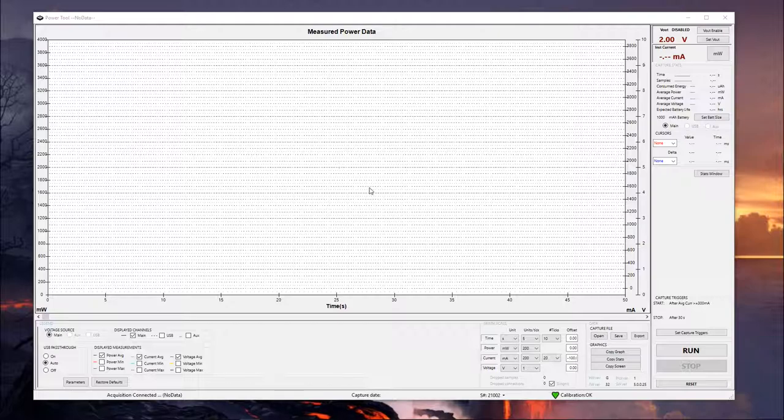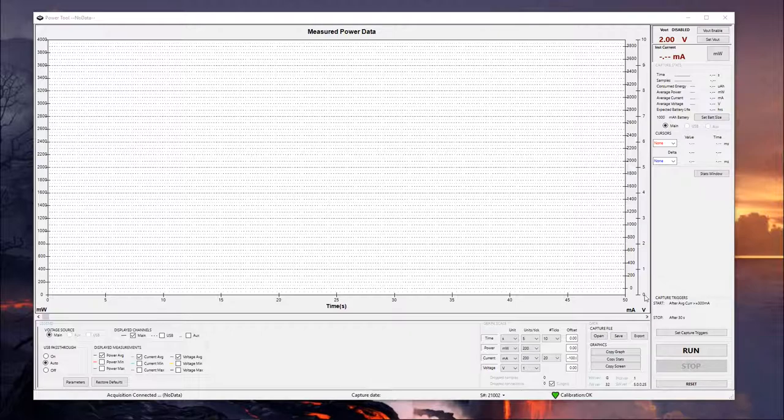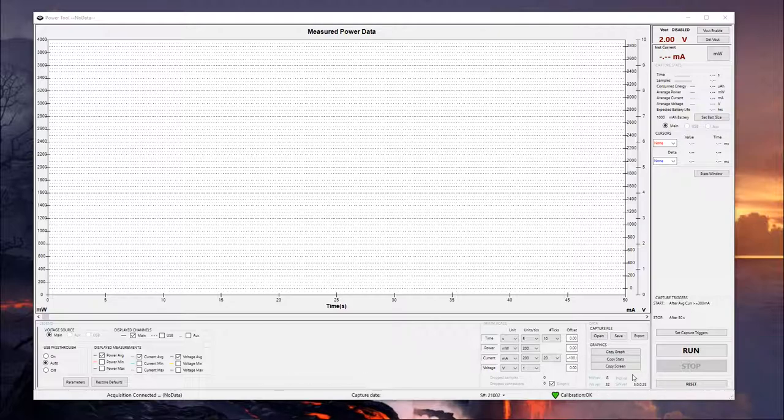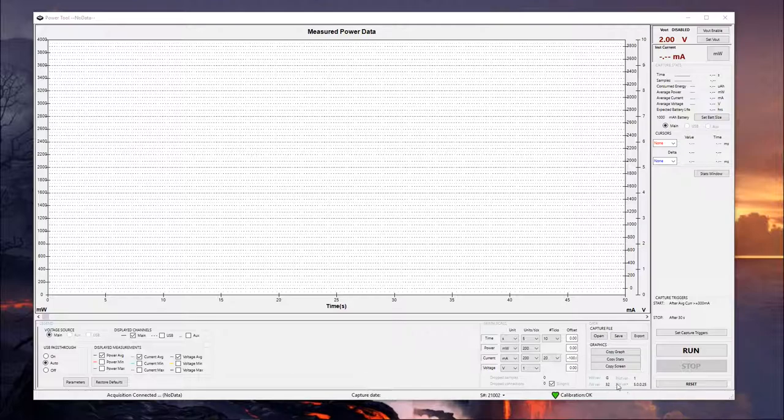When you first launch PowerTool, you've already installed a power monitor and you've got all that good, it's going to pop up with this screen right here. The easiest way to tell if you have the drivers and everything installed properly is going to be this little box down in the corner here. As long as these are populated with something similar to what you see here, your hardware revision is either going to be F or G, and then your firmware version should be something similar to this. If there's zeros or question marks, there's something wrong with your driver installation.